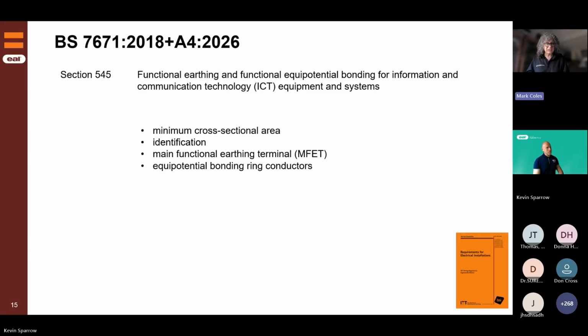As you can see on the screen, it has requirements for minimum cross-sectional area, and it mentions a bonding ring, big chunky kind of stuff in there. There's the identification of conductors, a requirement to have a main functional earthing terminal, and equipotential bonding ring conductor requirements, as I mentioned a moment ago. This is the kind of thing you'd find in a data center - somewhere you don't want any kind of corruption going on to the data they're dealing with, banks, that sort of thing. It's not a big chapter, but if you're involved in that area, it is quite important.